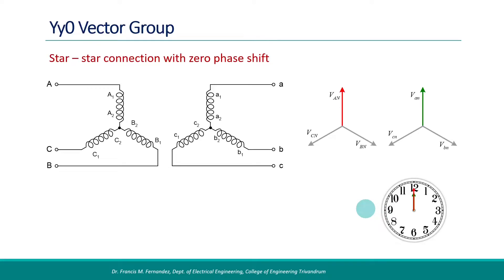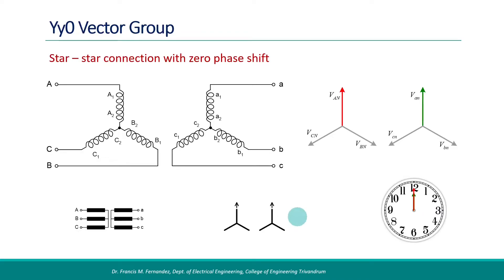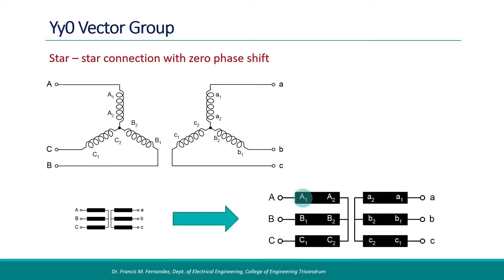We can have a simplified connection diagram, which will normally be printed on the transformer nameplate, and also a displacement diagram showing the connections on the two windings and the phase difference between them. In the simplified connection diagram, the polarities of each winding are represented with A1, B1, C1 on the left side for the primary, and A1, B1, C1 on the right side for the secondary. Primary terminals are represented with uppercase letters A, B and C, and secondary terminals with lowercase letters A, B and C. We shall follow this convention throughout this video.